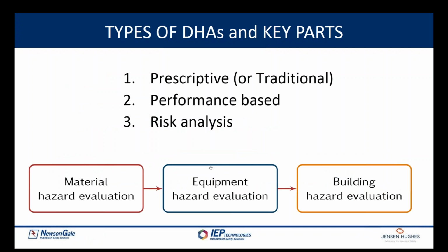There are three types of DHAs. I have a very brief amount of time available for this presentation, so I'll just quickly say that the prescriptive approach to DHAs basically involves looking at what's recommended prescriptively in the applicable NFPA standards and then offering recommendations to address gaps. The performance-based approach to performing a DHA and providing a defensible basis for safety is to show that if you have a different design that doesn't necessarily meet the prescriptive standards but addresses the objectives and the goals of the prescriptive requirements, and you can demonstrate that you meet those requirements, then that would be a performance-based approach.